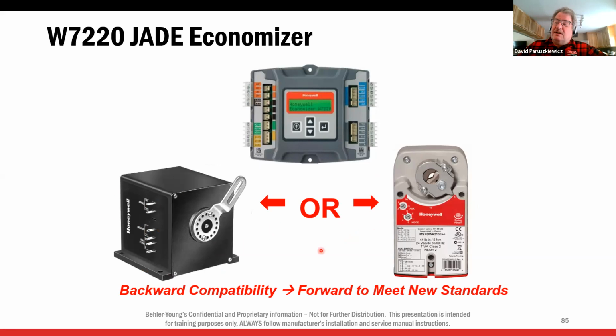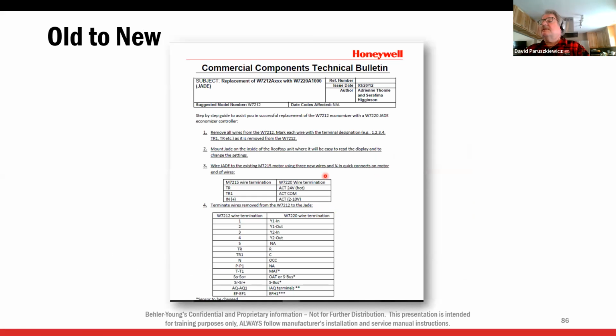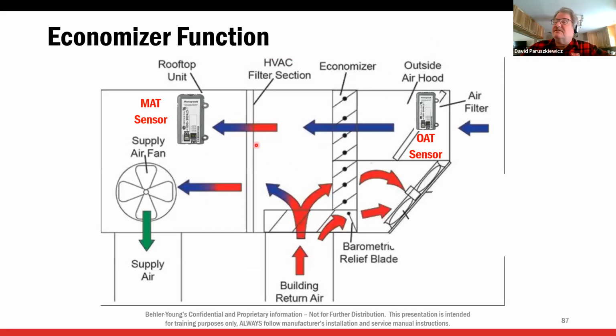The damper motors are backward compatible. So whether you have the old 7215 or the newer direct drive actuators, they are compatible with the Jade. All right. If you do a Google search or get a hold of me, this is a wire for wire swap. So if I have a 7212 and I need to switch it to the 7220, why? Because the 7212 has been discontinued. This is a wire for wire swap from the 7212 to the 7220. Again, you have to change the sensors.